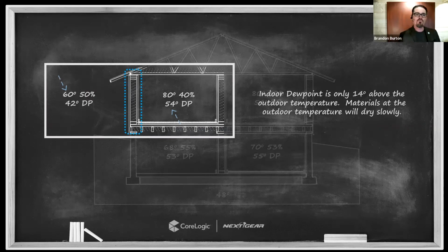And remember, if that gets a little complicated and a little muddy when you look at that, the simple way to understand it is just make sure you have at least 20 degrees. My 54-degree dew point, with my outdoor air of 60 degrees, if I wanted at least a 20-degree delta, the indoor dew point has to drop to 40. Or I have to ensure that that entire wall cavity is at least 74 degrees. Either one of those would give me the 20-degree difference.